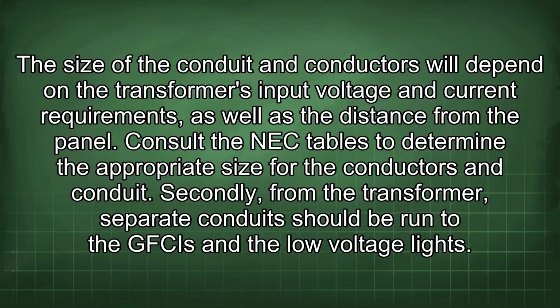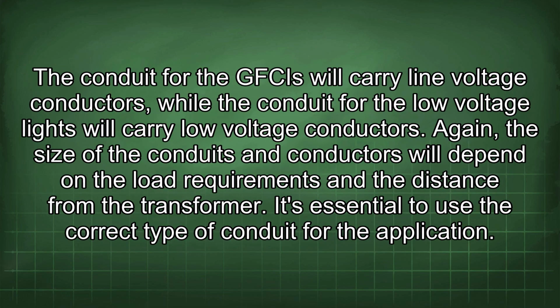Secondly, from the transformer, separate conduits should be run to the GFCIs and the low voltage lights. The conduit for the GFCIs will carry line voltage conductors, while the conduit for the low voltage lights will carry low voltage conductors. Again, the size of the conduits and conductors will depend on the load requirements and the distance from the transformer. It's essential to use the correct type of conduit for the application.